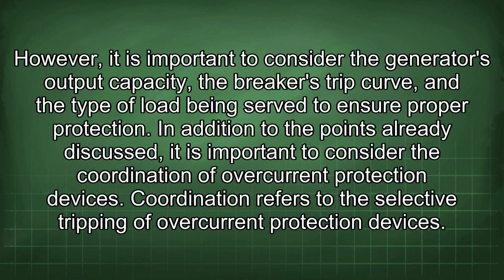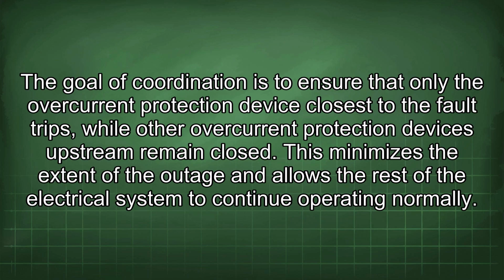In addition to the points already discussed, it is important to consider the coordination of overcurrent protection devices. Coordination refers to the selective tripping of overcurrent protection devices. The goal of coordination is to ensure that only the overcurrent protection device closest to the fault trips, while other overcurrent protection devices upstream remain closed. This minimizes the extent of the outage and allows the rest of the electrical system to continue operating normally.